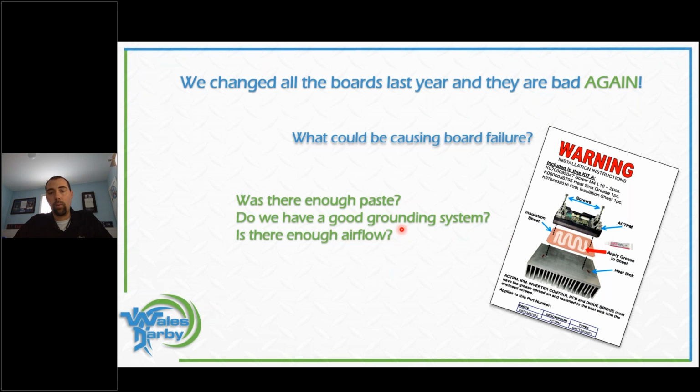We can also have a bad grounding system. Your ground might be great, and all the work you did was fine. We've got good solid wires from indoor to outdoor. But especially where we are in Long Island, near the shore, you've got grounding rods in sand, and all that salt and everything else in the air eats them up, sometimes within a year or a couple years. Maybe the electrician only put one grounding rod where that soil needed multiples, right?